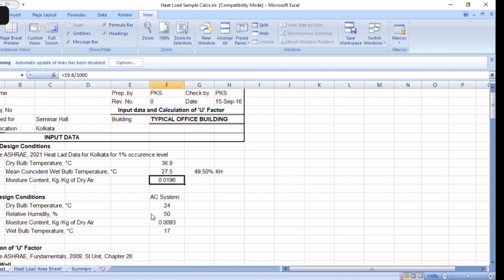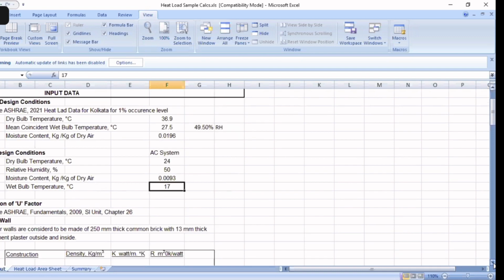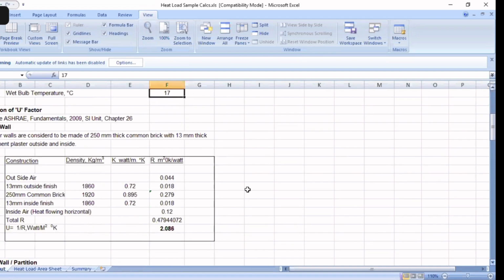Then inside temperature I have considered 24, RH 50. Again from the psychrometric chart I have found out the moisture content and the wet bulb temperature inside. Then calculation of U factor. For wall: outside still air, plaster, brick, inside plaster, inside still air. So this was the total R and this is the total U, 1 by R.